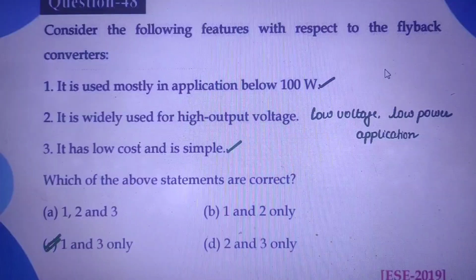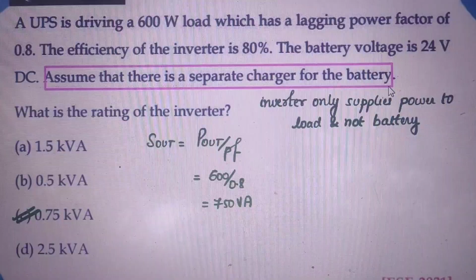An uninterruptible power supply is driving a 600 watts load which has lagging power factor 0.8. Efficiency is given as 0.8. Battery voltage is 24 volts DC. Assume that there is a separate charger for the battery. What is the rating of inverter? Rating is nothing but he is asking about the apparent power. Apparent power is equals to real power by power factor. You will get 750 volt ampere. Here the note point is inverter only supplies power to the load and it does not supply to the batteries.